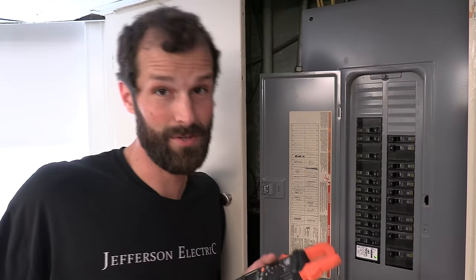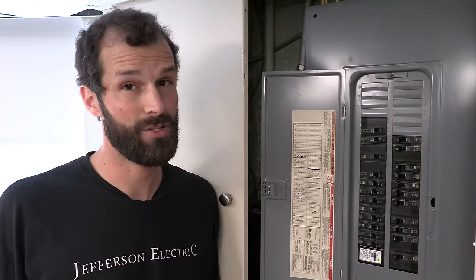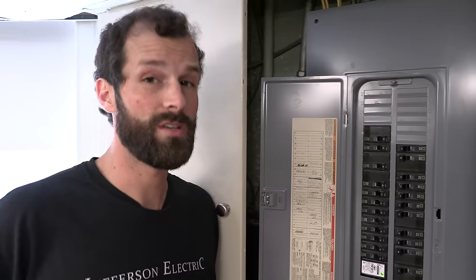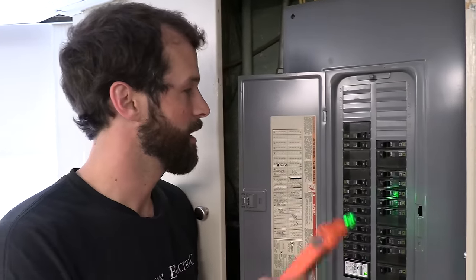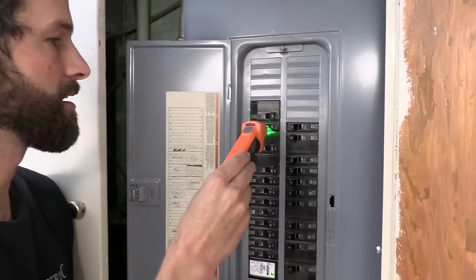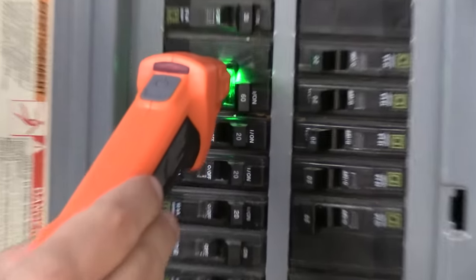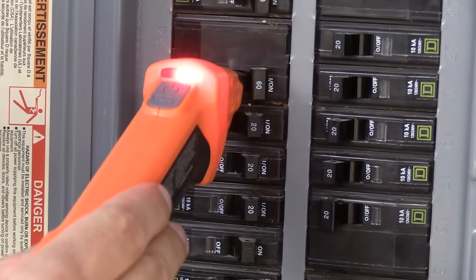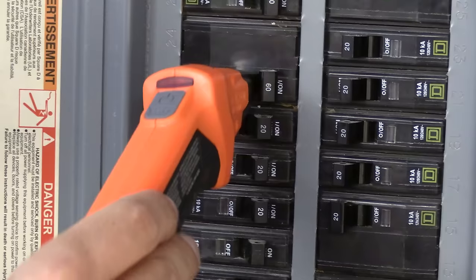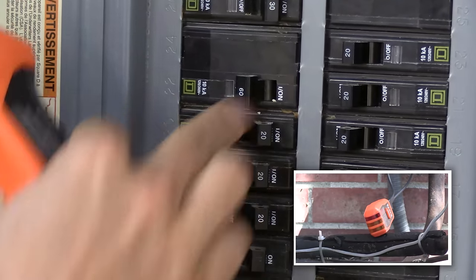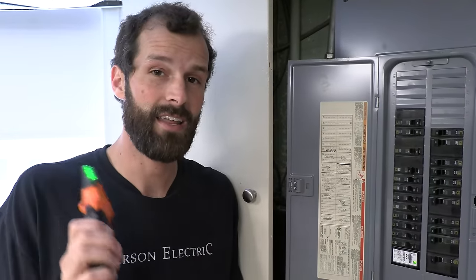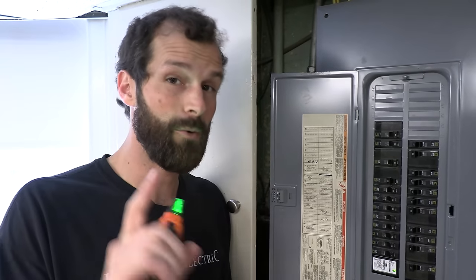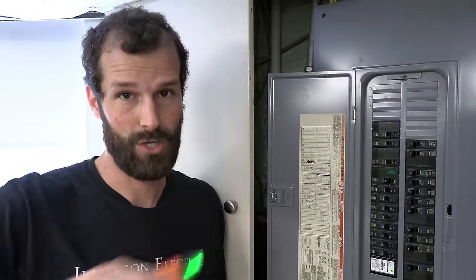So this is a big power circuit. Like I said, it's physically a large air conditioner. It's probably going to be on a two pole 40, 50, or 60 amp breaker. Check out my 40, my 30, my 60. Boom. Now what you can expect is that the voltage outside when taking a reading will drop to a nominal zero. It might bounce around with a few millivolts. That's negligible. That will be an indication that power has been turned off.